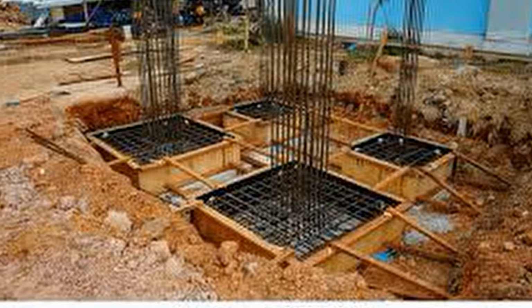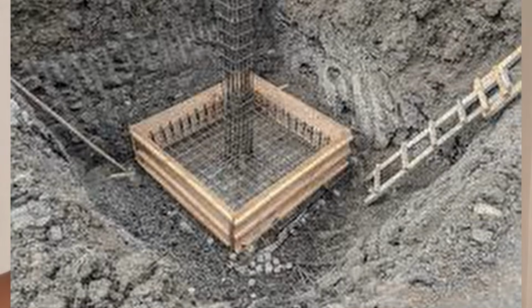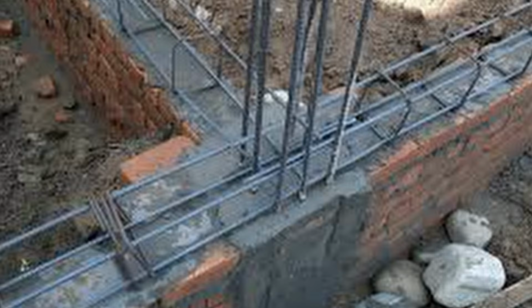When they do the balustrades, they knock out the concrete and they weld the balustrade metal to the steel rebars in the columns. Right? So everything is connected together. The balustrade metallic work is connected to the rebars in the column. The rebars in the column are connected to the foundational reinforcement rebars. And then the foundational reinforcement rebars have concrete over them. And then they have the copper tapes connecting them to the various services I talked about earlier on, which obviously is in contact with the soil as well. So the whole house becomes the same potential zone. Everything bonds to one common earth system. If you have separate earths, it can cause voltage differences, and that is dangerous.